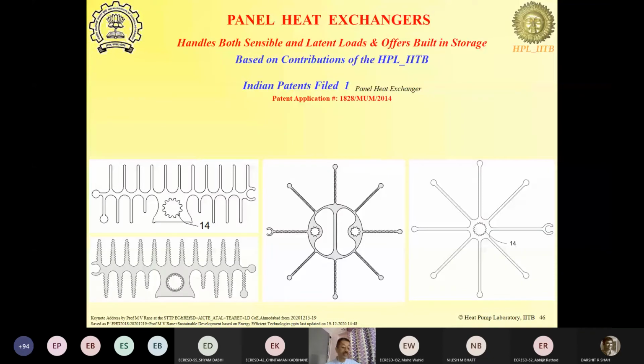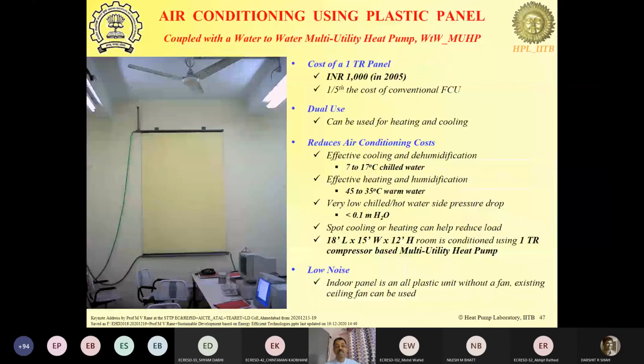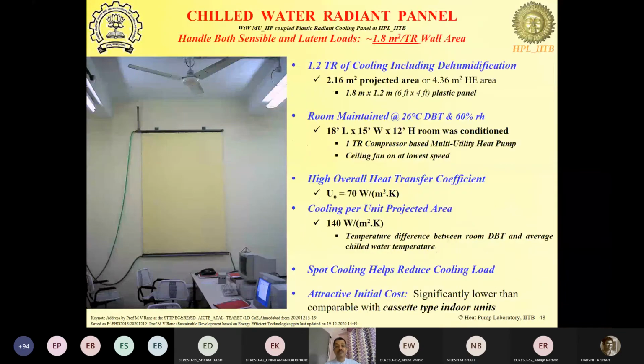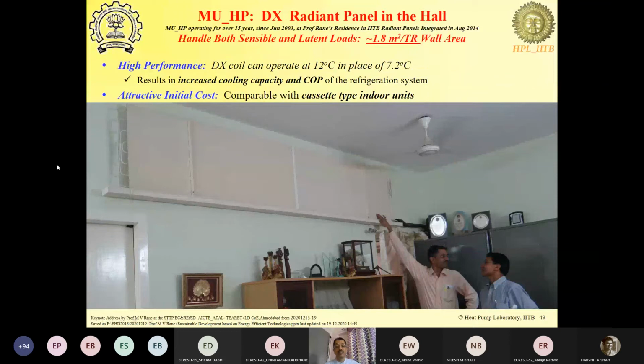These are some panel heat exchangers which we have deployed for air conditioning. In fact, the panel which you see behind me here in my bedroom has been installed here for more than 6 years, and without any servicing, it has been performing quite well. Every day, this is integrated with the heat pump which I have. So these are some examples of the panel heat exchangers. This is another panel installed in my dining area. This is a different type of panel. And we are able to dispense about 1.8 in 1.8 meters square frontal area. We are able to dispense 1 ton.